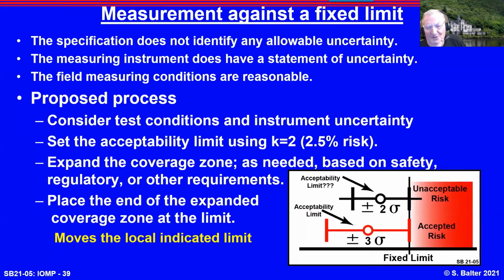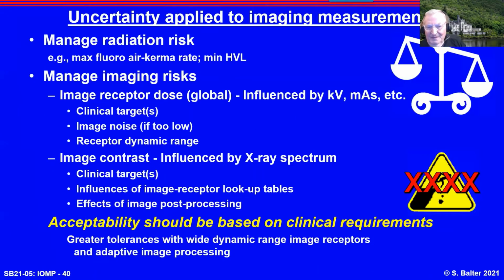Typically, people will use the 2 sigma, perhaps the 3 sigma if something is critical. And you do this by accepting the limit. On the system I'm installing now, to keep peace with the regulators and their processes, I've asked the installer not using his process to go above 90 milligray per minute at the reference point, which gives me very high assurance that no matter whose instrument is used to test it, I won't be above the regulatory 100.